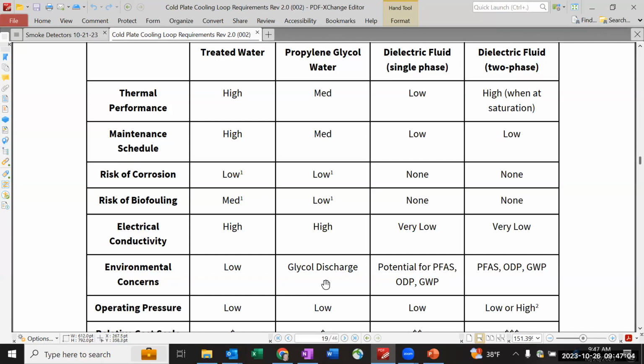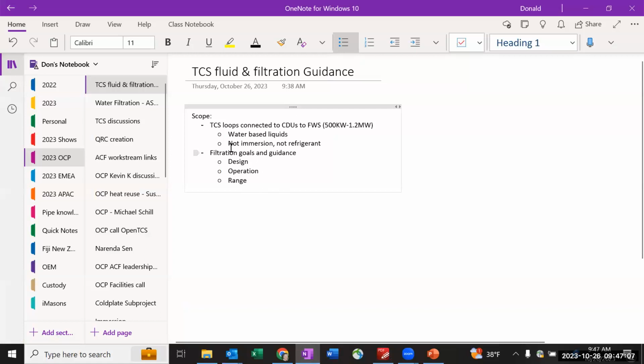Let's go back to the real quick overview. My goal is to have something that helps people understand the difference between how you approach 100 micron versus 50 micron versus 25 micron filtration, with an ultimate goal based on what I read from Lawrence Berkeley National Lab: you basically go with 50 micron filtration and a side stream filtration of say 5 or even 1 micron. So your main flow goes through one filter, but through repetitious flushing you eventually get your filtration well below that. Does that make sense?